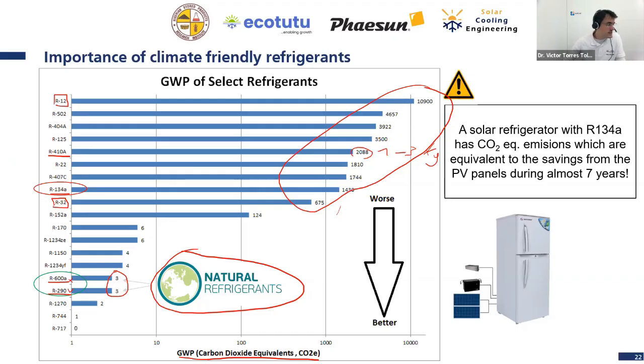What is the difference with R-600a? Well, there is a difference in global warming potential, here between 1,400 and 3. This is clear for everyone. The other difference is that they have different working pressures and so on. So you cannot use the same compressor. You cannot use the same fridge. You need to change the fridge, the compressor, and so on, because they work at different pressures, different condensing temperatures, evaporating temperatures, and so on. So they have a different thermodynamic cycle. I hope that's answering the question.